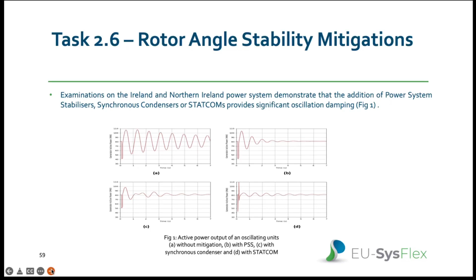The recommended mitigation of damping oscillation is based on reduction of decay time as well as reduction in peak overshoots. The results demonstrate that the addition of PSS and STATCOM provides significant damping, while a slightly more limited mitigation is observed for the synchronous condenser.